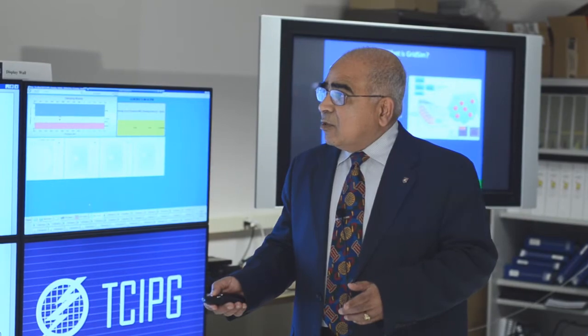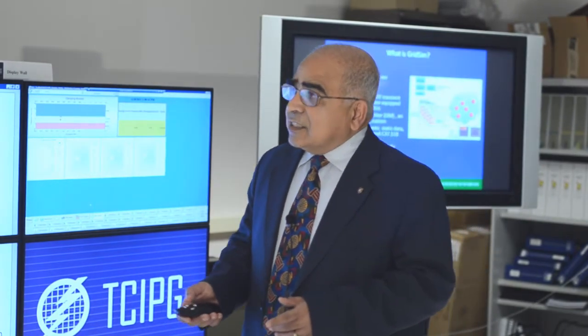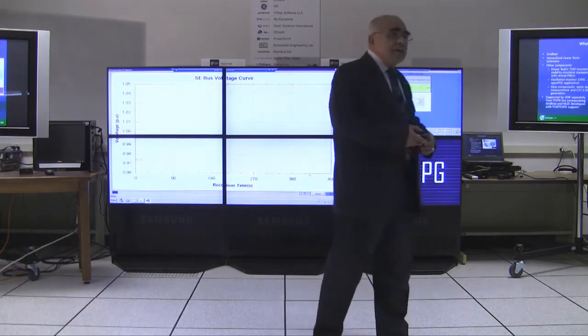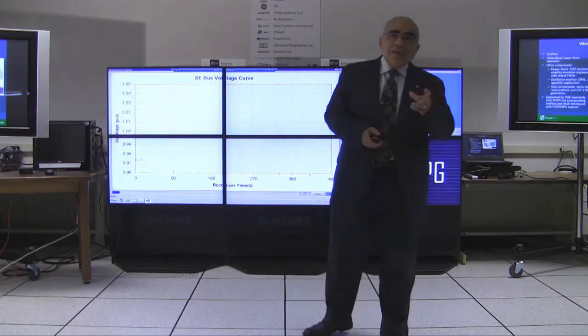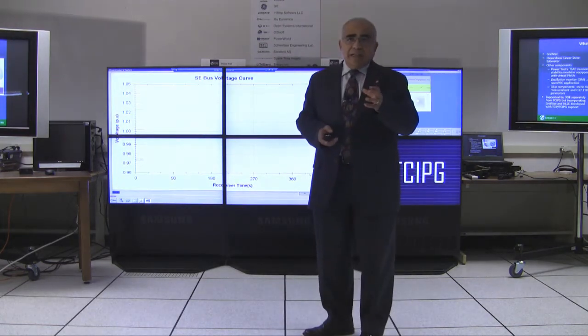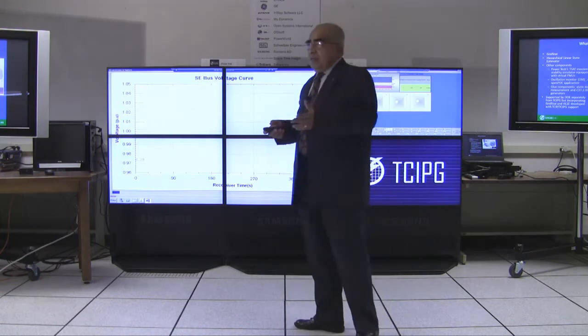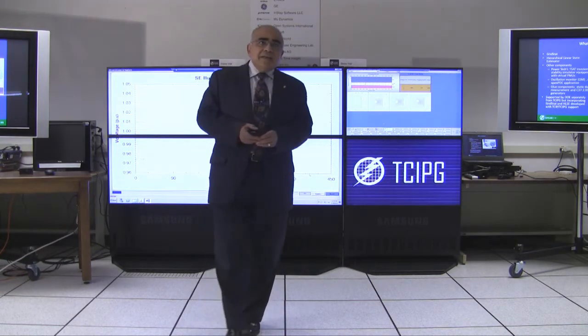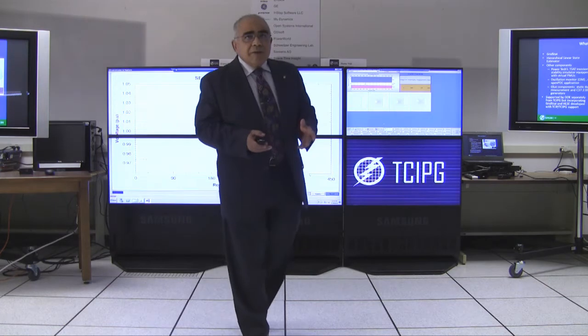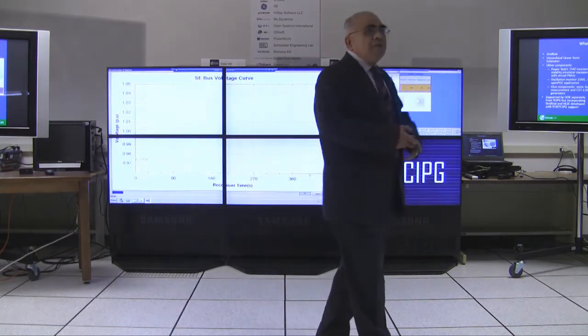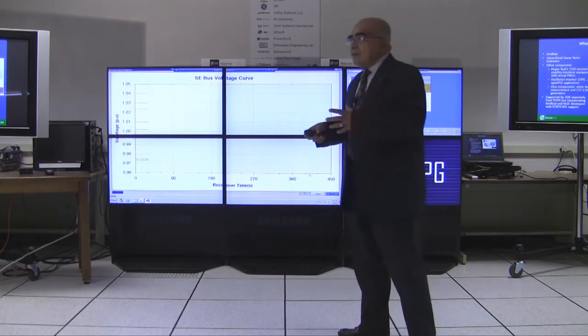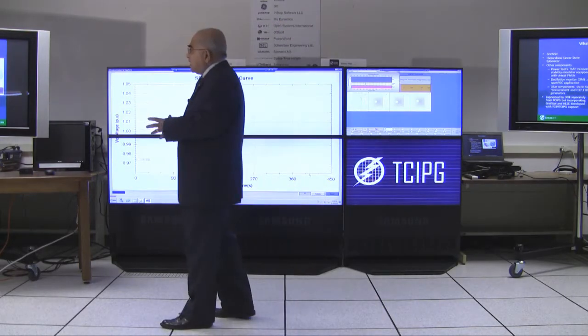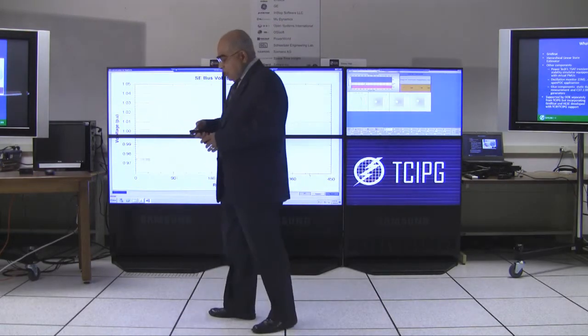One application is the oscillation monitor and the other is the state estimator. The oscillation monitor requires PMU data at 30 times a second but not from every PMU. On the other hand, the state estimator requires data only about five times a second but from all PMUs. So you have different sets of requirements for these applications, and GRIDSTAT sorts out how to handle that.